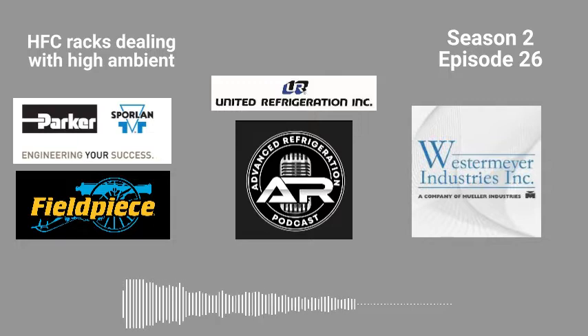So guys, also be aware on the older legacy stuff, stuff that's like 20, 25 years old. You'll see a lot of times Tyler condensers. Well, Tyler didn't make a condenser. What they did was they subbed it out to WIT, which is Russell or HTPG, I believe that's the short name for one of the companies that were in there. But those Tyler condensers for the racks, very, very particular on the fan blades. There's a certain pitch, certain amount of fan paddles, and if it wasn't correct, you'd end up just burning up a bunch of freaking motors. And typically it was because it was completely compacted. But once again, it was like Kevin said, hey, just this one's good. This one will work. Same thing.